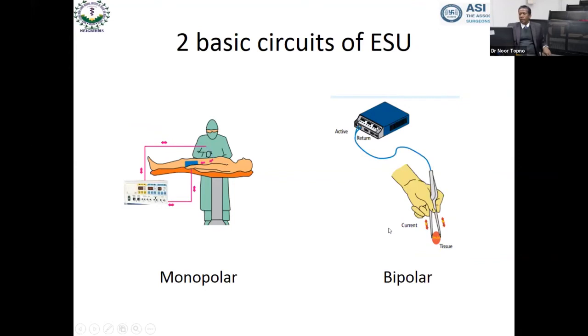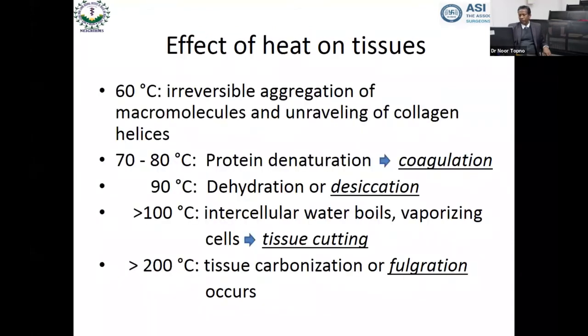Now again, there are two basic circuits of the electrosurgical unit, the monopolar and the bipolar. You see the current flow here is coming to the patient, and through the patient electrode it comes out and then goes back to the generator. And again from the generator, it is coming into the patient. In the bipolar, the flow is over a very small area between these two arms of the instrument that is being used. So it's considered the monopolar can be more harmful, but bipolar technically is considered much safer.